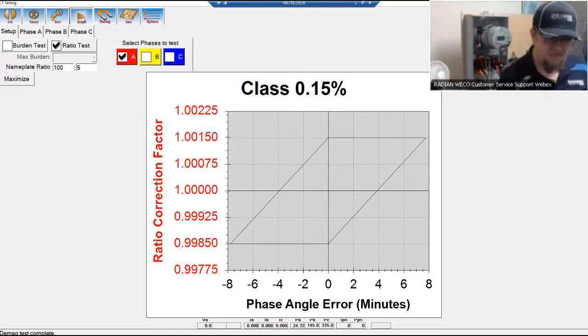We recommend doing that if you are getting some high results, but as a point to that, if you run the demag, it will change your ratio of the CT. So as a little disclaimer, if you do run the demag on it, expect a change in your ratio when you run that.